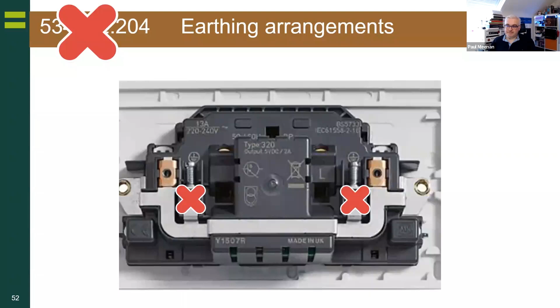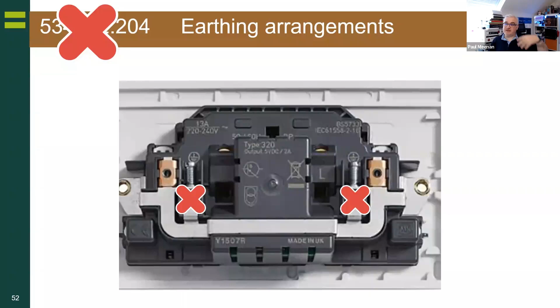One of the other small changes: earthing arrangements, dual earthing terminals in the back of most sockets. That regulation has been deleted. Quite important. Because now if we comply with the 6 milliamps and the RCD protection and the DC immunity, do we need it?